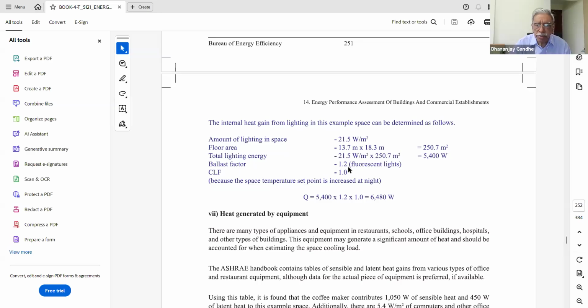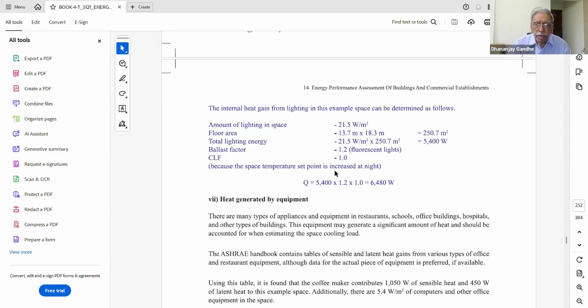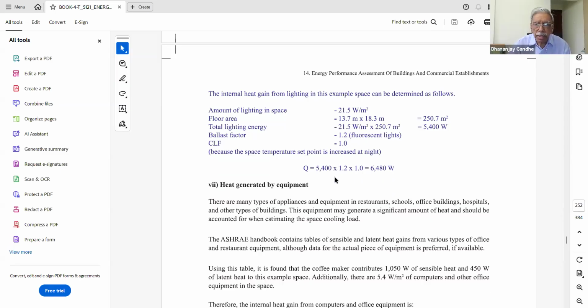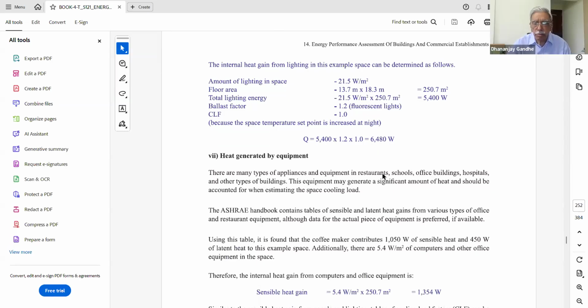And the fluorescent ballast factor is to be taken as 1.2 for the fluorescent lamp, and CLF is to be taken as 1. So the heat gain from lighting is 5,400, the lighting load in terms of watts, multiplied by the ballast factor 1.2, multiplied by CLF 1, is equal to, so the heat load is 6,480. That's how it works out.